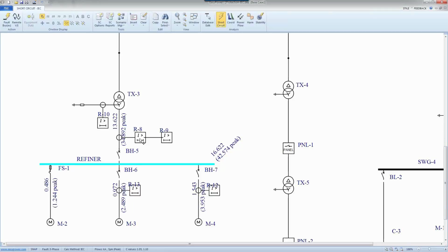So let's make it simple. If you had only one branch, not all these things, only one branch, and you replace the X with 0.4X, and then again you divide the result by 0.4, you would get the X value again. And that's exactly the case. If you have only one branch for method C, you would see that the peak value would be equivalent to the peak value coming from method B most of the cases, and in fact it would be as if you don't even apply any 0.4 factor.